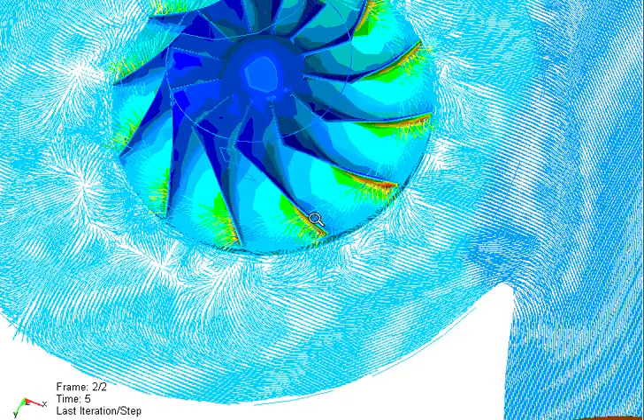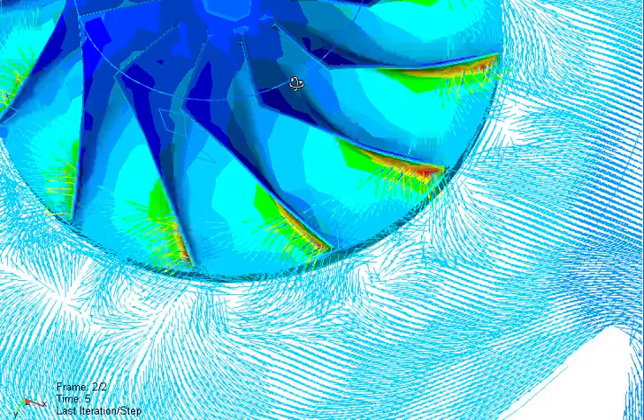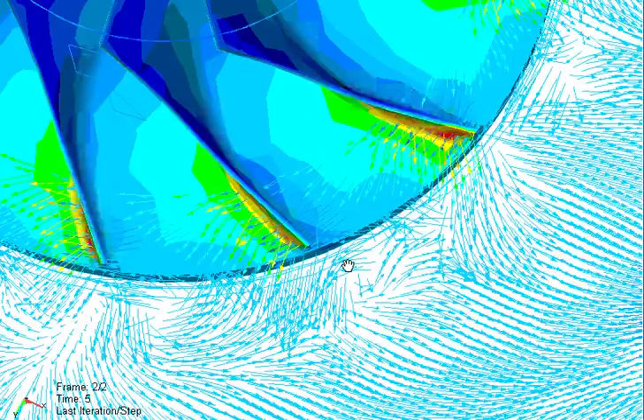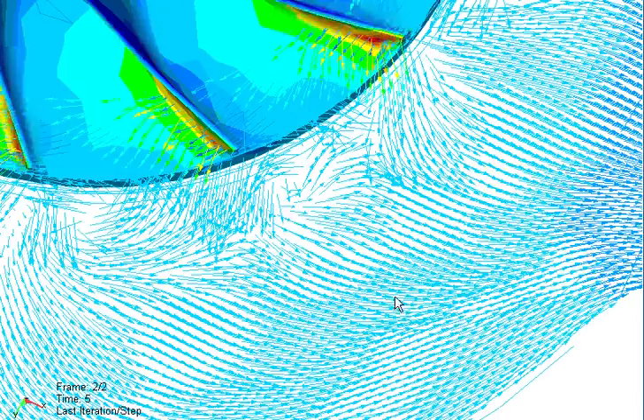As we're seeing this compressor here, if you look closely at these little vectors screaming through the volute, in one design we added stator vanes. So they're actually locked into the volute housing, the casing.